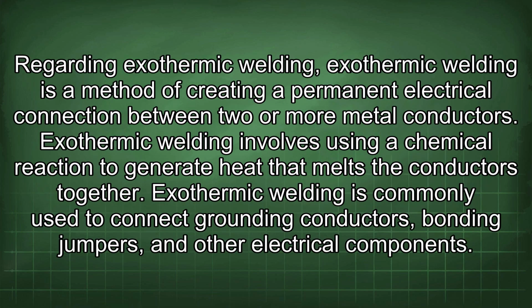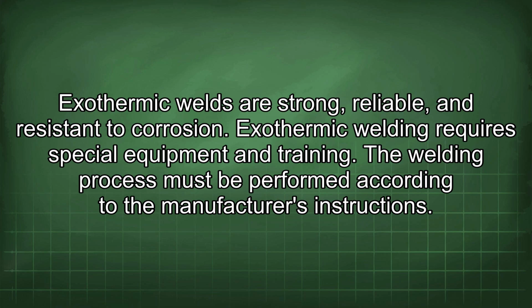Regarding exothermic welding, it is a method of creating a permanent electrical connection between two or more metal conductors. Exothermic welding involves using a chemical reaction to generate heat that melts the conductors together. Exothermic welding is commonly used to connect grounding conductors, bonding jumpers, and other electrical components. Exothermic welds are strong, reliable, and resistant to corrosion. Exothermic welding requires special equipment and training. The welding process must be performed according to the manufacturer's instructions.